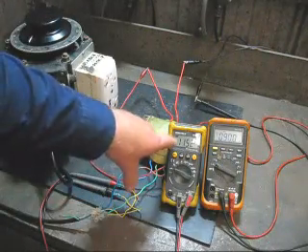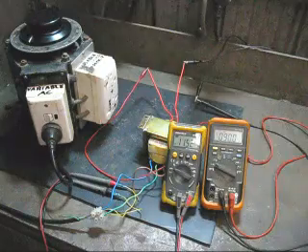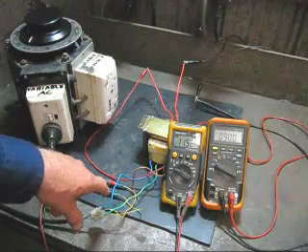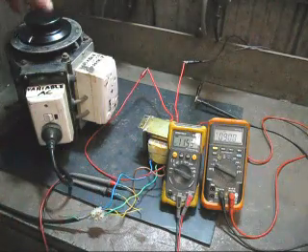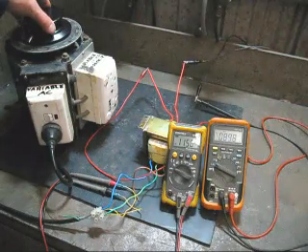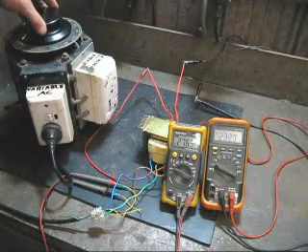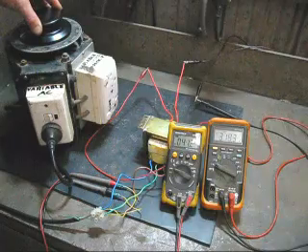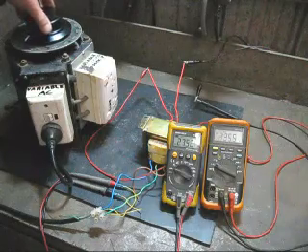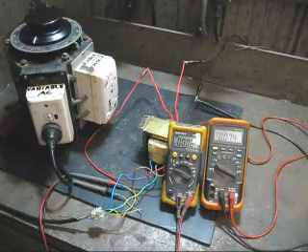We have got 11.5 volts here and 90 volts on there, and I know something is wrong — I can't go much further. But if you do go further, the Variac makes a loud humming noise. I will give you a demonstration. It is making a loud humming noise now and I have to back off very quickly so you don't burn out the Variac.